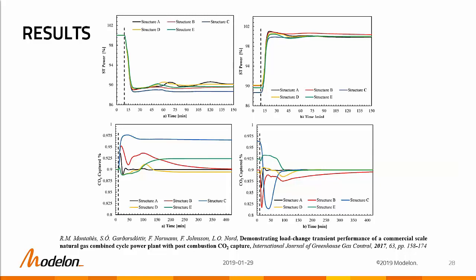And as you can see, you have several trajectories in different colors, which represent the trajectories for the same load change when you have different control structures implemented in your capture plant. On the right, we have a similar scenario, but in this case, the gas turbine load is increased, and consequently, the steam turbine power output also increases in the combined cycle, and you also observe a transient in the capture rate.